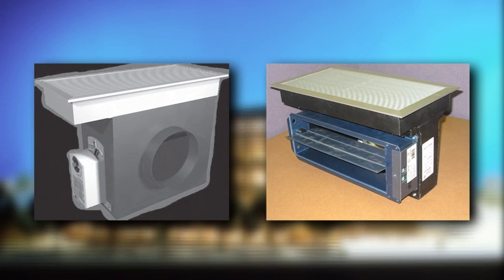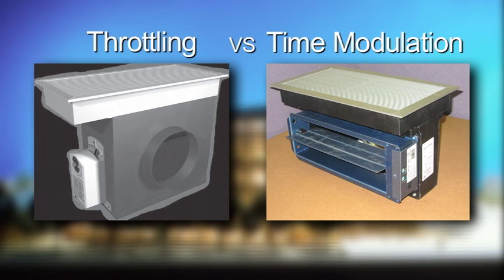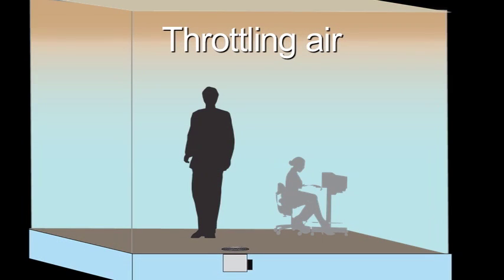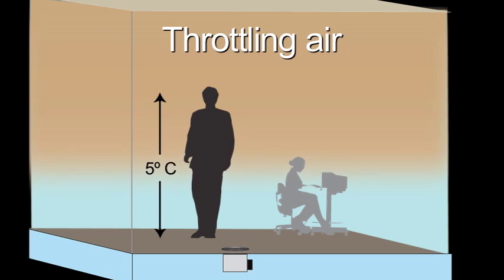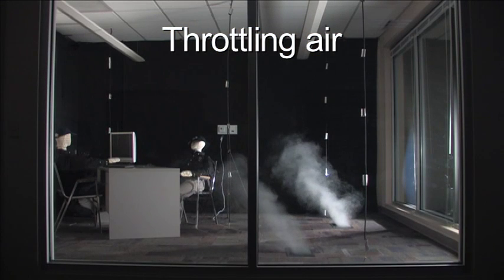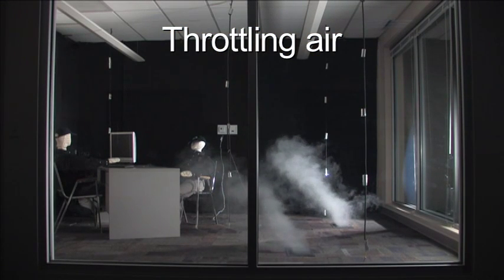Let's now consider a comparison of throttling as an air control method versus time modulation. With throttling of air, a diffuser's throw height and distance drop as the volume is modulated. At low or part loads, these diffusers pool cold air, causing large head-to-toe differences. In reality, how often are space conditions at part load? Nearly all the time. This diffuser is operating at about 25% airflow.